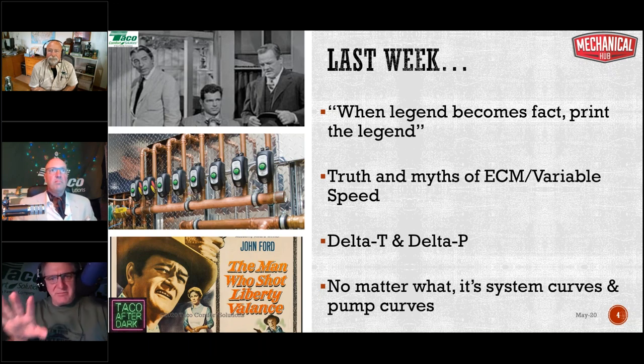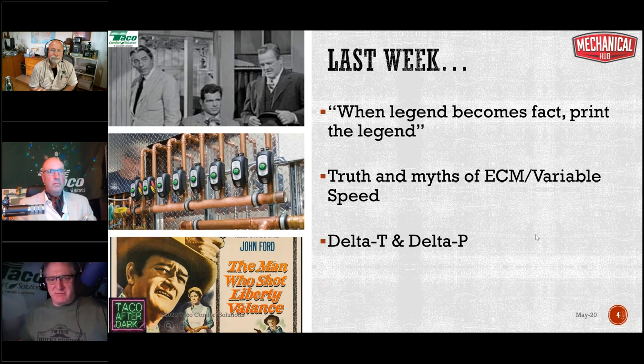And the biggest takeaway I want you guys to remember is that whether we're talking delta T, delta P, or a fixed speed circulator, it all comes down to the interaction between system curves and pump curves. You can't escape that interaction. Systems work where system curves say they're going to work, or where pre-programmed algorithmic performance curves say the system is going to work. The circulator makes that decision. The circulator enforces that reality. So it's not that the system's going to do what the system's going to do. That's a lot of nonsense. The system's going to do what the circulator says it's going to do. Now, we have ways to manipulate that and make it work in our favor, but don't ever forget that. That's maybe the most important part.